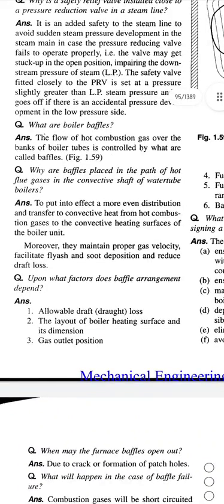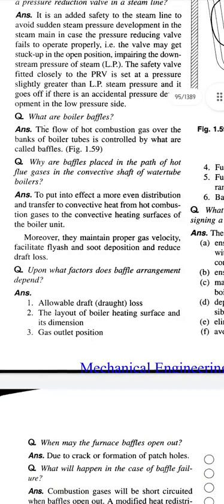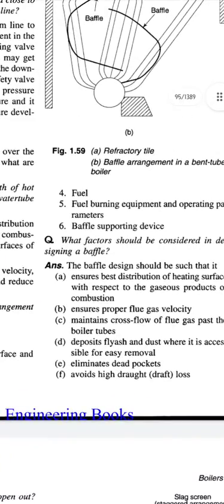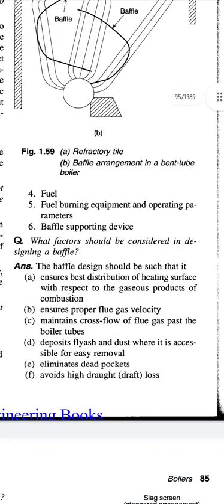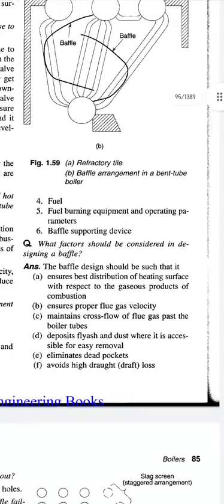Question: upon what factors does baffle arrangement depend? Answer: allowable draft loss, the layout of the boiler, heating surface and its dimensions, gas outlet position, fuel burning equipment and operating parameters, and baffle supporting device.